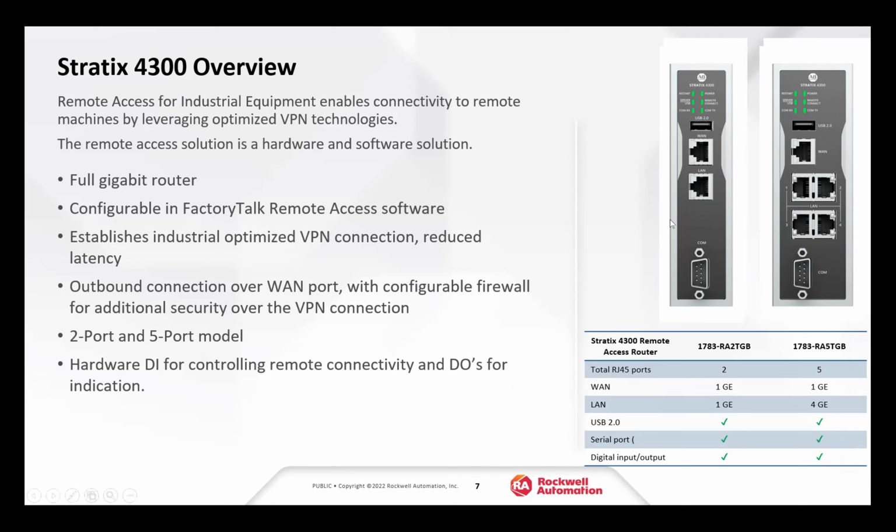If you look on these devices here, they have a serial port on each one. They support RS-232, 422, and 485 connections. So if you have some legacy equipment that you're looking to connect to, if they have serial port communication, that would be a way to get connectivity. The USB port, the way it's released right now, is more for configuring the setup and updating firmware. So that's not able to be used for a USB to serial converter. It's not used for that at this point.